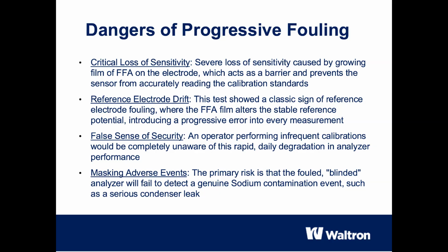First, we see a critical loss of sensitivity. The film on the electrode acts like an insulating layer. The electrode loses its ability to respond to concentration changes, which is evident by the decreasing calibration strength. Second, we have reference electrode drift. The film clogs the porous junction of the reference electrode and changes its potential. Since every measurement is a comparison to the reference electrode, every successive measurement is inaccurate.